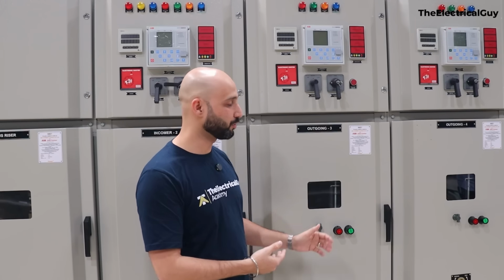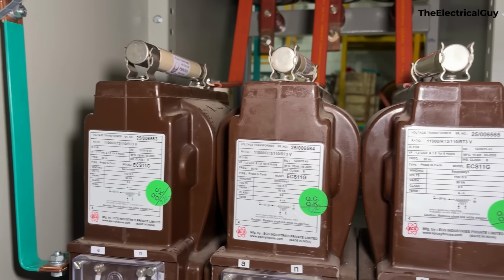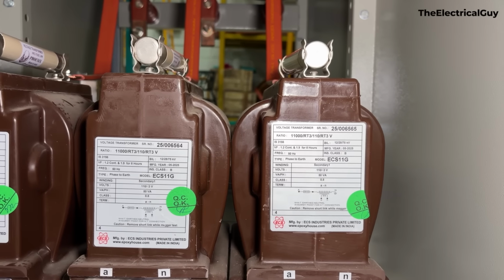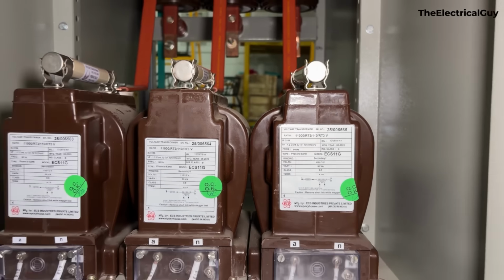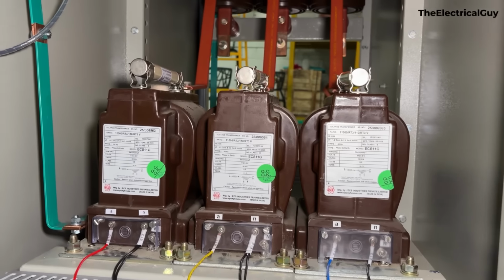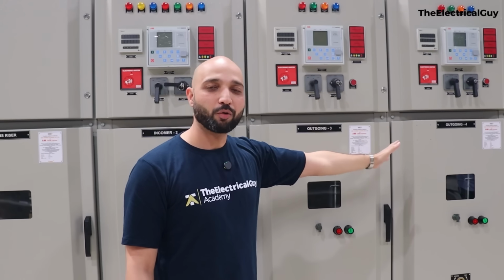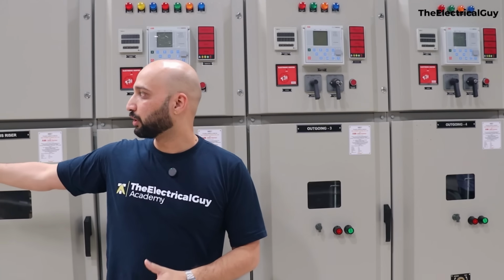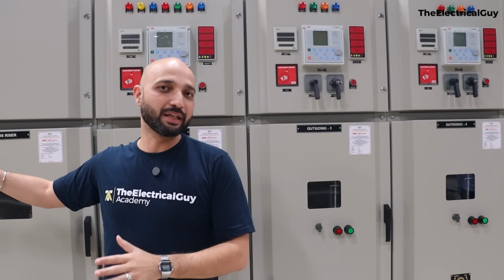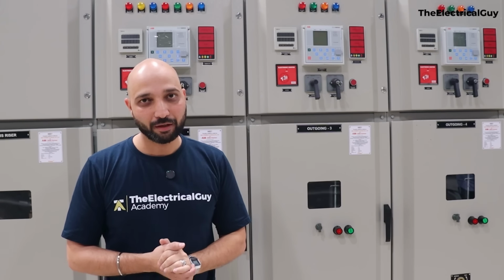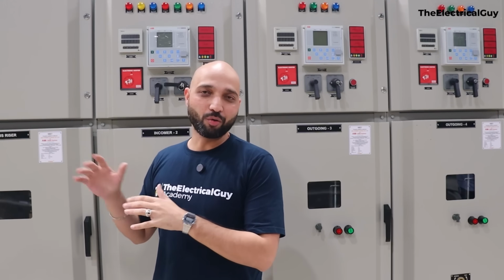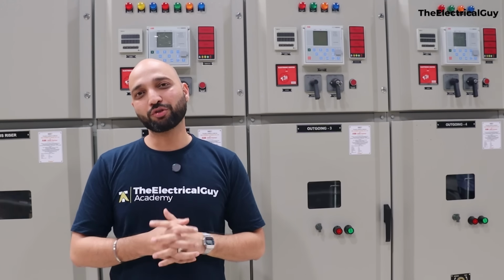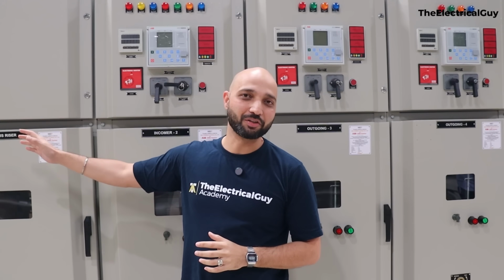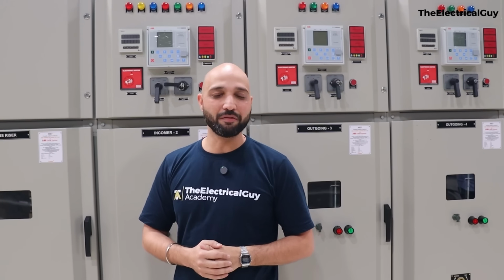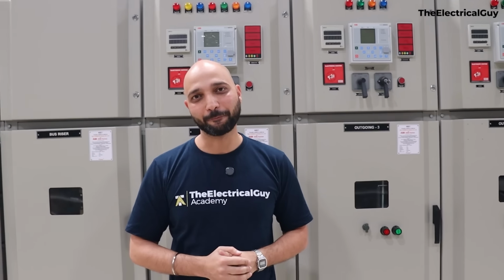The reason is obvious, because we are getting the supply directly from the VT that we have in Incomer 2, and that will be fed to the relays and the meter, right? And then the outgoing will go. Exact same panel you will find in outgoing 4, and both the 2 outgoing panels that we have are exactly identical with each other, right? So those are Incomer and outgoing panel. Now coming to the most confusing part of the switchgear panel, and that is the bus coupler and bus riser. Let me explain why we need this and why we use it.